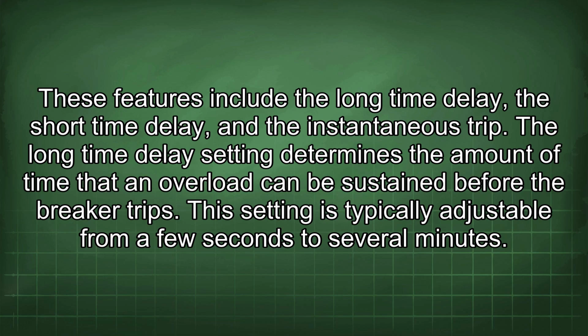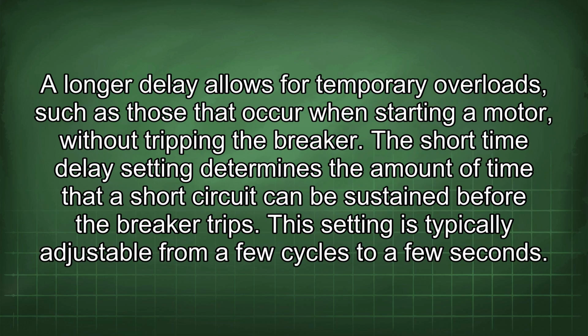These features include the long time delay, the short time delay, and the instantaneous trip. The long time delay setting determines the amount of time that an overload can be sustained before the breaker trips. This setting is typically adjustable from a few seconds to several minutes. A longer delay allows for temporary overloads, such as those that occur when starting a motor, without tripping the breaker.